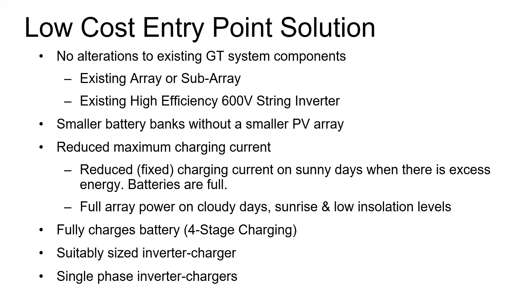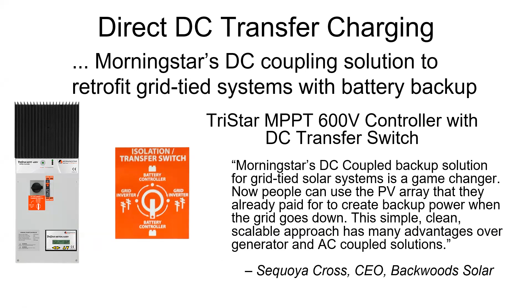This is the direct DC transfer charging solution from MorningStar. It uses our TriStar MPPT 600 volt controller with the transfer switch. There are two versions available: one is just the controller as shown here, with the built-in transfer switch, and the other comes with a pre-wired GFPD, which is nice for ground fault protection requirements and safety per NEC. It represents good value having all of that incorporated into one product.